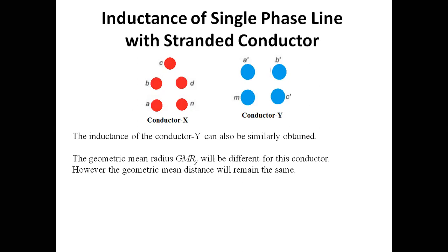Here, what we do, we consider multiple strands of aluminum outside, and we take the steel strand inside in the core portion to give the mechanical strength, and due to skin effect most of the current will pass through the surface, so there we give the aluminum conductor, good conducting material. So all these conductors are stranded conductors, therefore the stranded conductor is very useful.